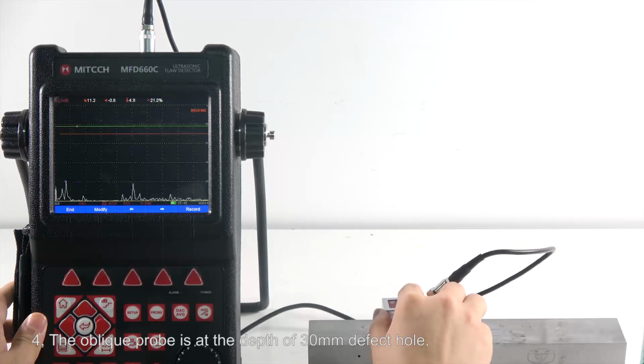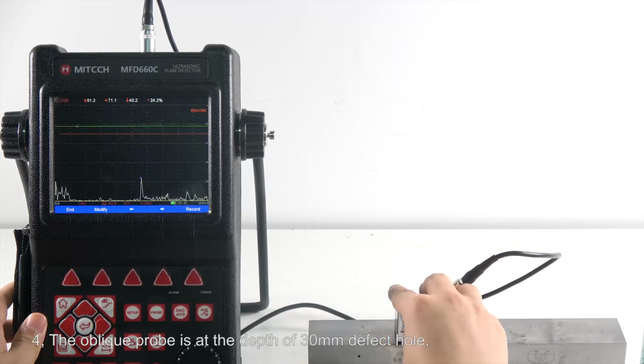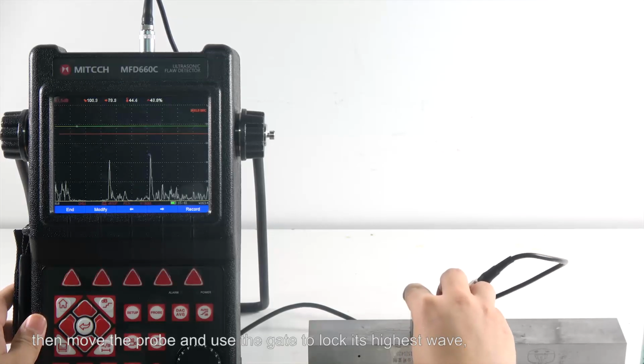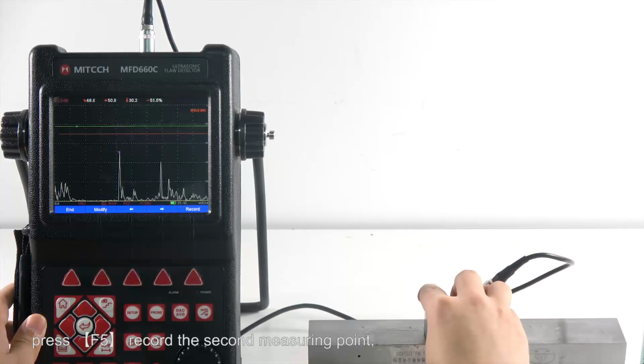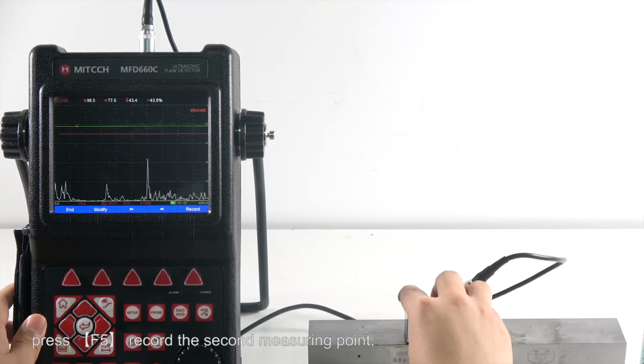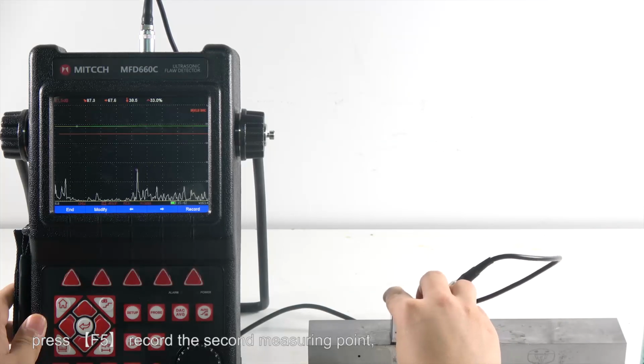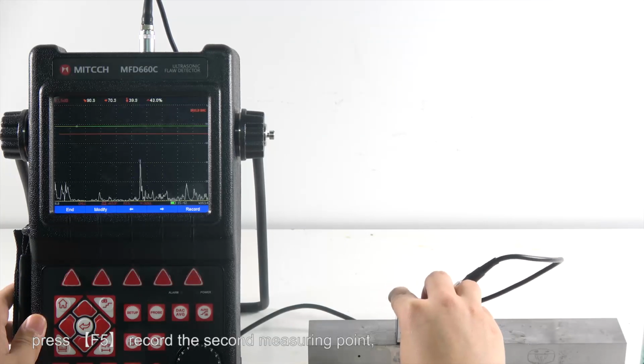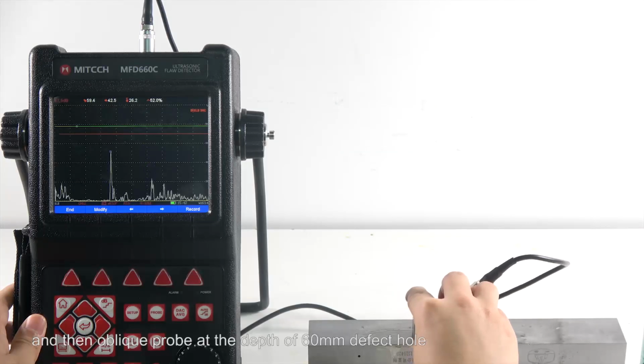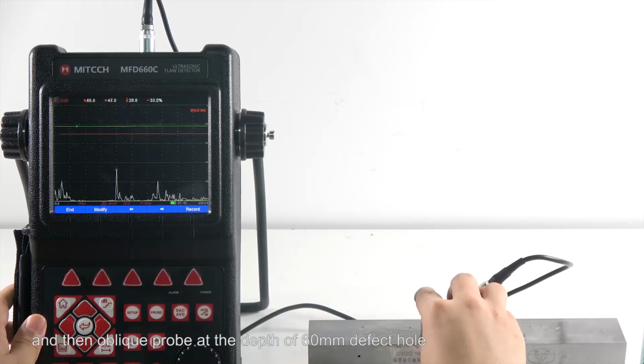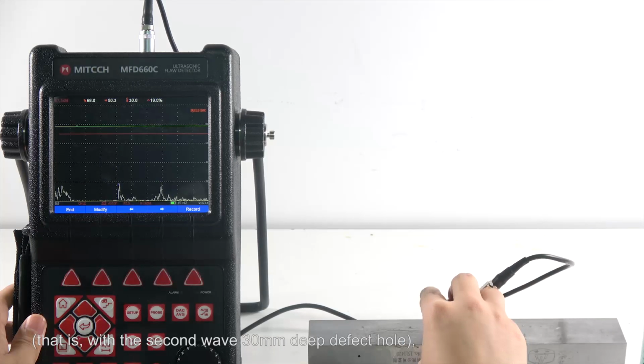Then place the oblique probe at the 30 mm depth defect hole. Move the probe and use the gate to lock its highest wave. Press F5 to record the second measurement point. Then place the oblique probe at the 60 mm depth defect hole, that is, with the second wave of the 30 mm defect hole.